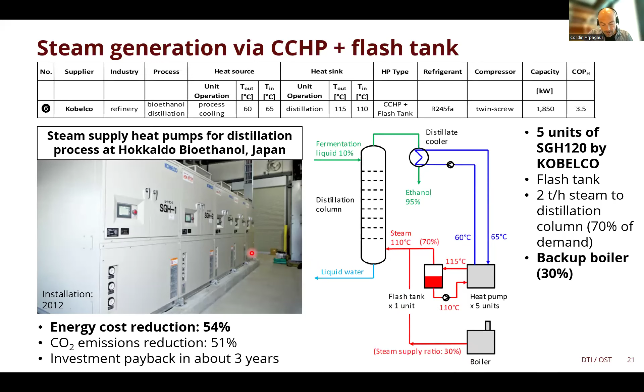This demonstration case is a steam generating heat pump with closed cycle and flash tank combination. It is an application for distillation of bioethanol at Hokkaido in Japan. So these are 5 units of the Kobelco SGH 120 heat pumps, and they were installed in 2012, 2013, so already over 10 years in operation. And so the heat pumps are arranged in parallel so that they can increase the capacity. The heat source is the distillate cooler at 60 degrees, and the heat sink is steam at 110 degrees. And the heat pump covers around 70% of the steam demand. And there is still a backup boiler, and this would cover maybe 30% of the heat demand. So the customer is very satisfied with this solution. It's a very reliable solution with the heat pumps.